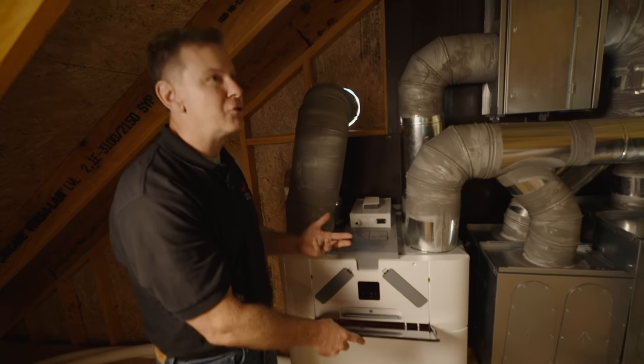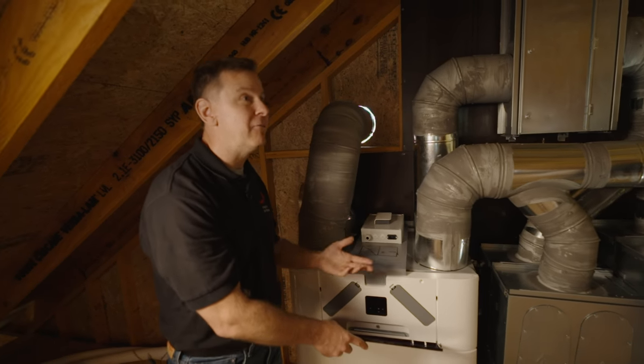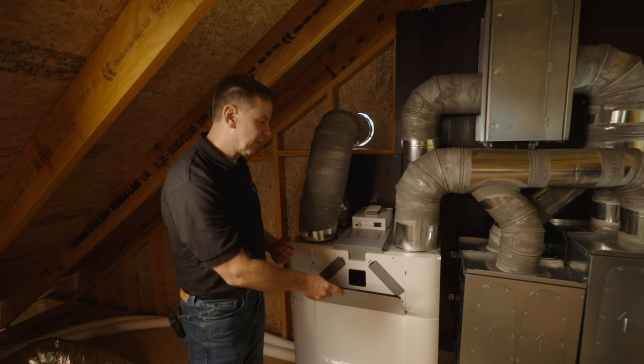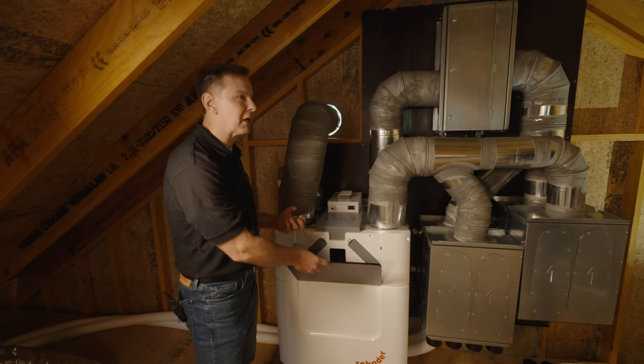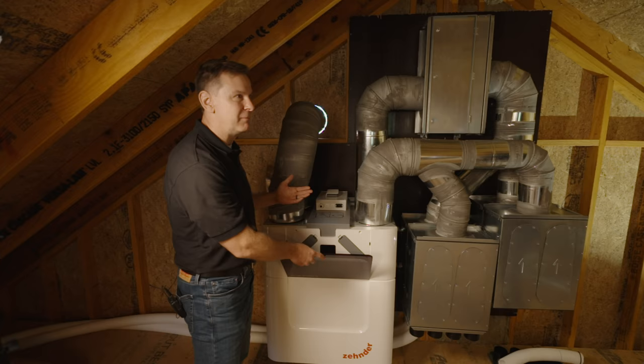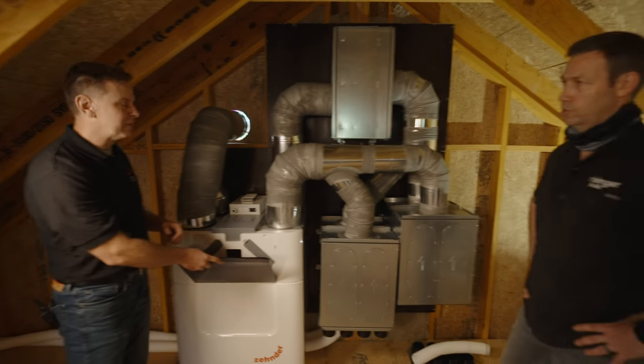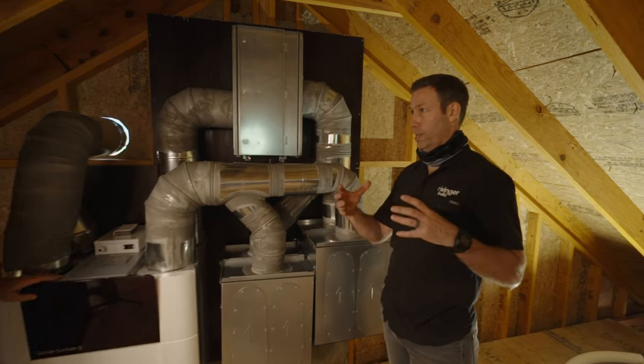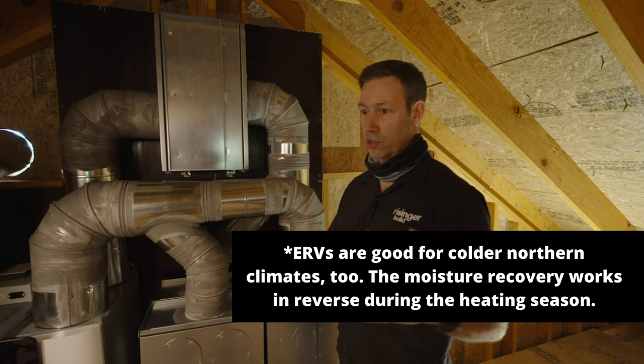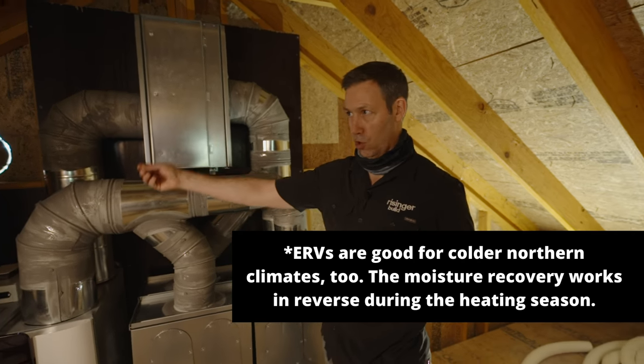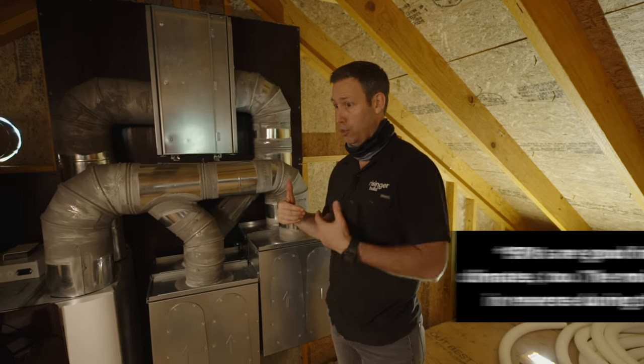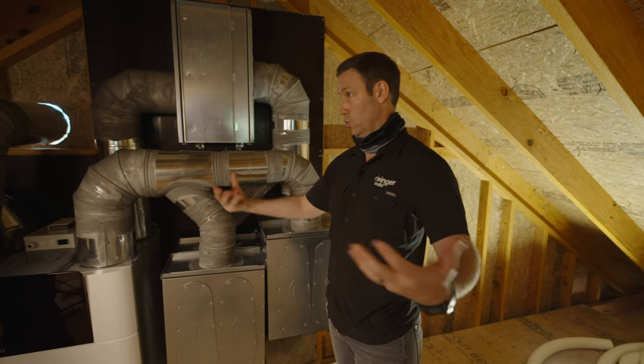But what you're trying to do is ventilate, and you're trying to control that ventilation. You want to do it with energy recovery, otherwise you might as well just leave the windows open. So if we're in the north, we're worried about just an HRV, a heat recovery ventilator, because generally in really cold climates it's low moisture outside. But here in the south, in the southern US, often it's really humid out.